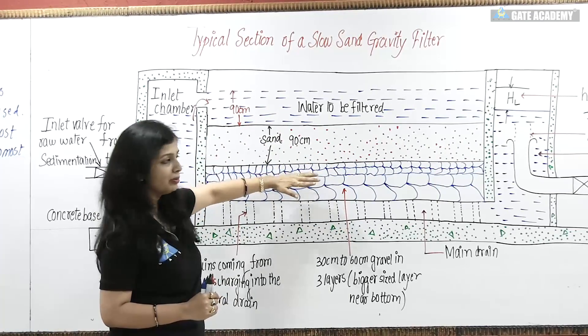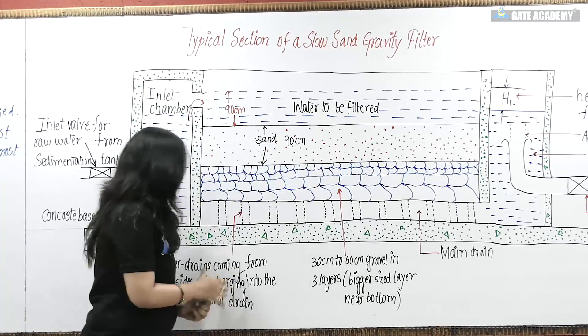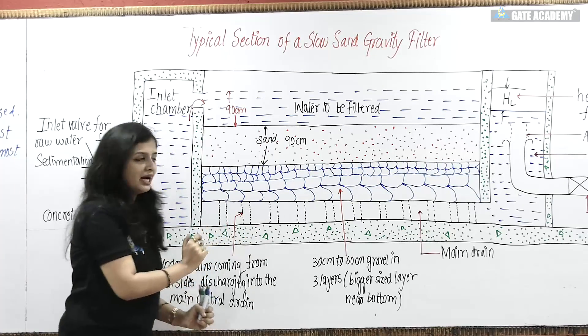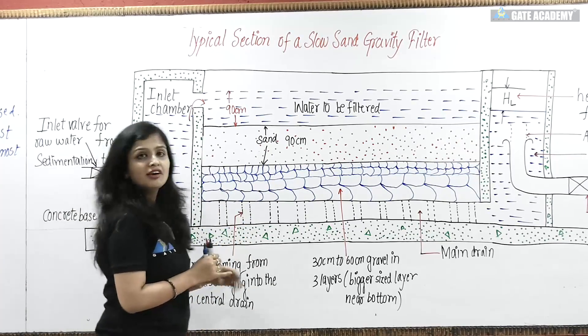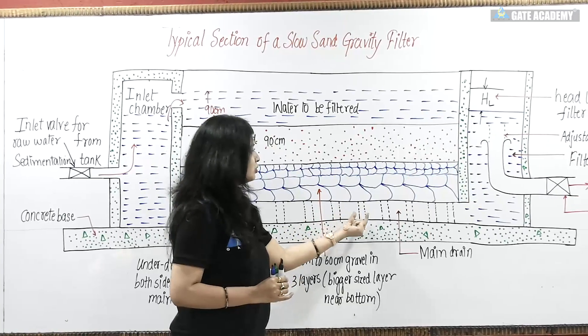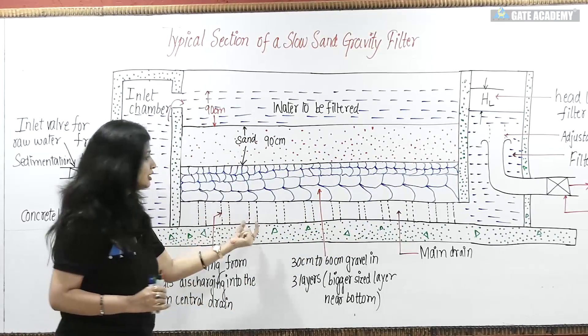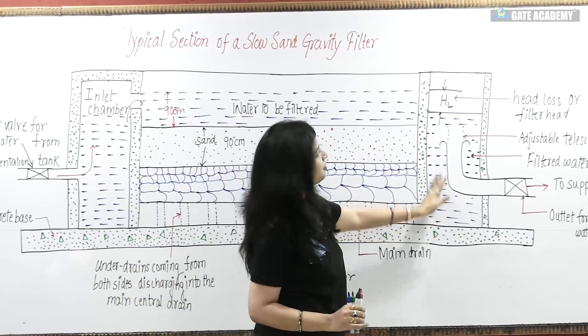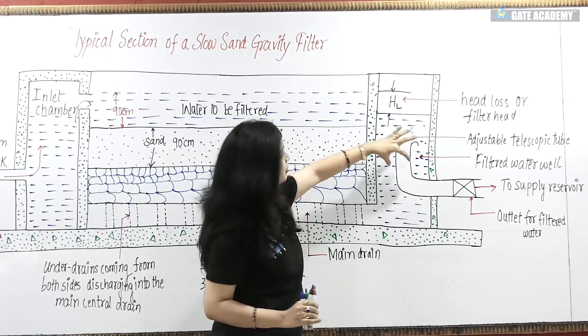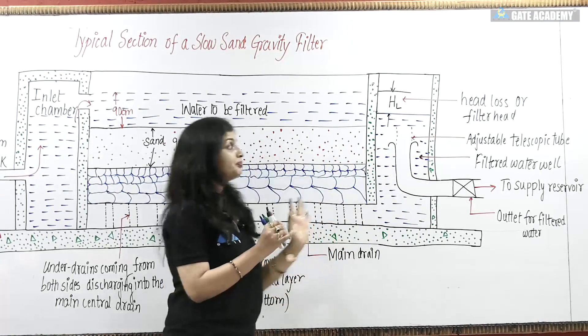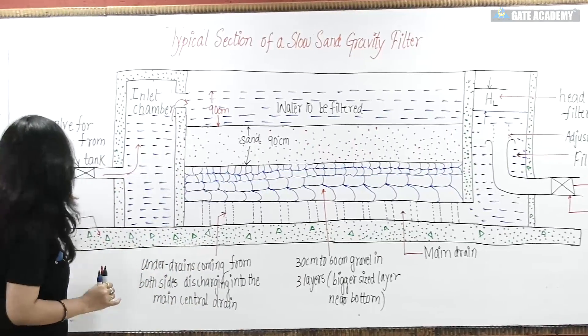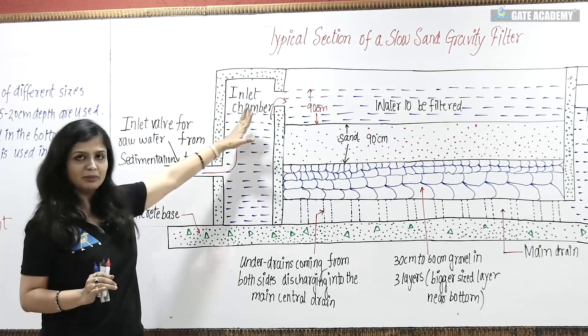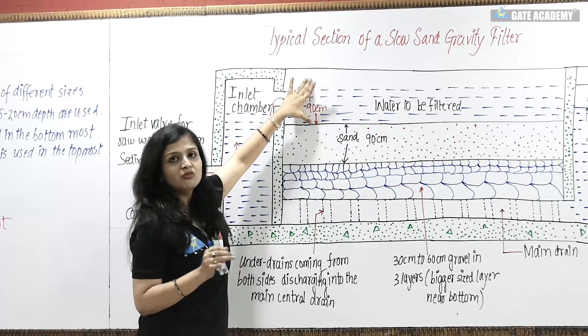You can see the finer gravel at the top and coarser gravel at the bottom. The under drains are 3 to 5 meters apart with a slope provided. These under drains lead to the main central drain, which purifies and passes water to the main drain, and from there it goes to a filtered water well. And then there is a telescopic tube. First, the inlet water from the plain sedimentation tank goes to the inlet chamber, and then this water goes to the filter beds.